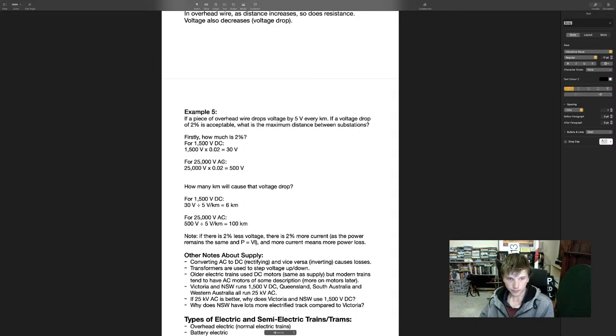For the 25 kilovolt system, well, 25,000 times 0.02 is 500 volts. Okay, so, you know, that's quite a bit more. We can drop by up to 500 volts before we need to boost it.